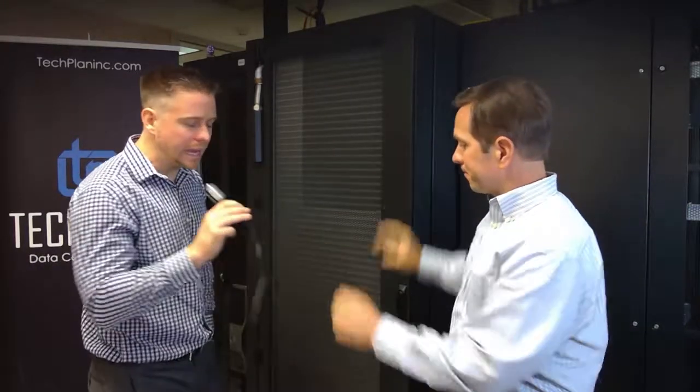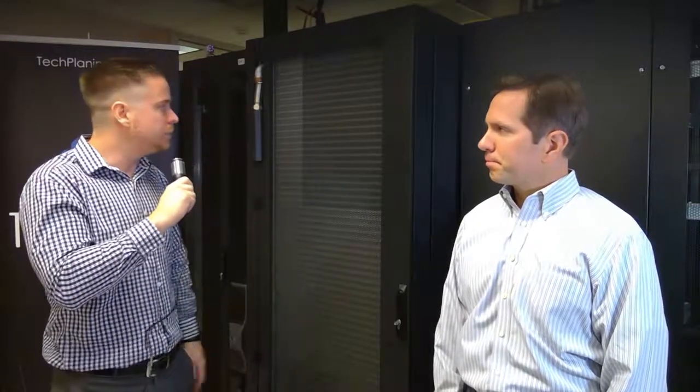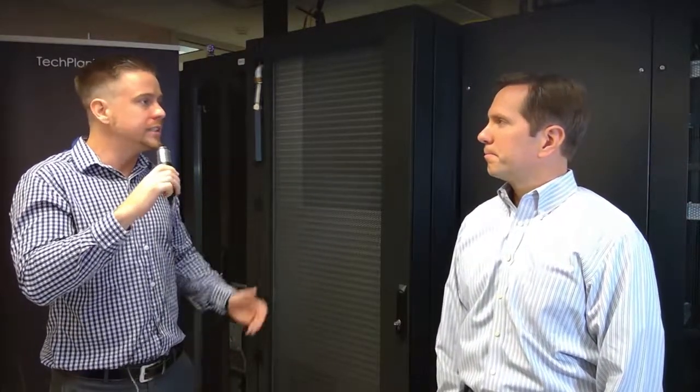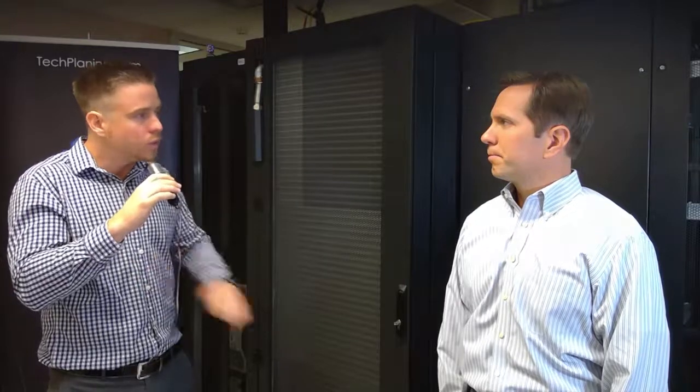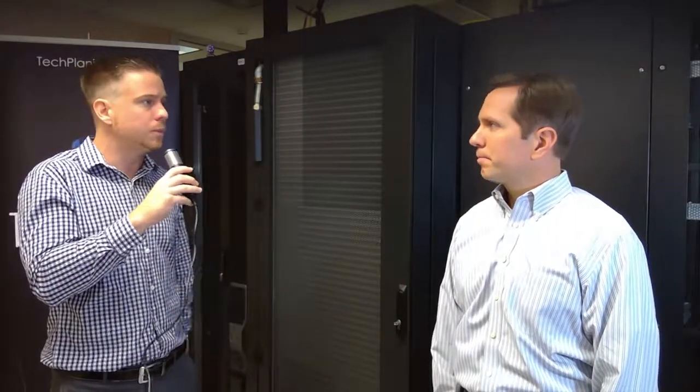Awesome. And that's a really key point because the average heat load density for a server cabinet is about 7 to 10 kW. So this is obviously designed to cool and reject the heat of much higher capacities, 35 and 50 kW. So what's the application for this? Why would you want to use a rear door heat exchanger versus a typical data center with a raised access floor with the cooling from the subfloor plenum?